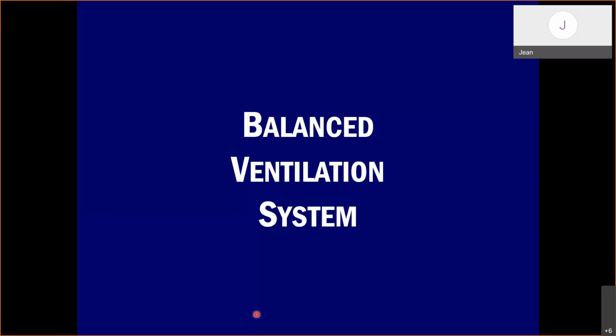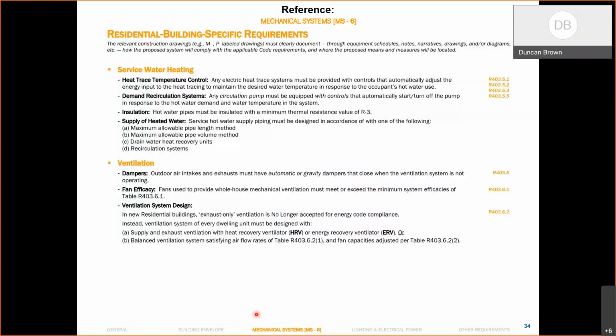Back to you, Duncan. So yes, we also wanted to talk about the ventilation system design, in which there are residential specific requirements for the new energy code. Next slide, please. So although the 2014 New York City Mechanical Code does not have this requirement, the 2012 International Mechanical Code and later versions require that when buildings are tighter than 5 air changes an hour, mechanical ventilation is required. The New York City Energy Code requires residential buildings to not exceed 3 air changes an hour, and therefore the trigger for mechanical ventilation requirement comes into play relative to the IMC.